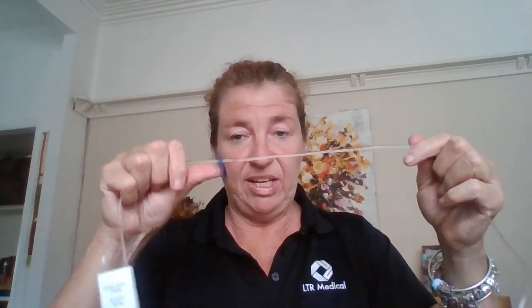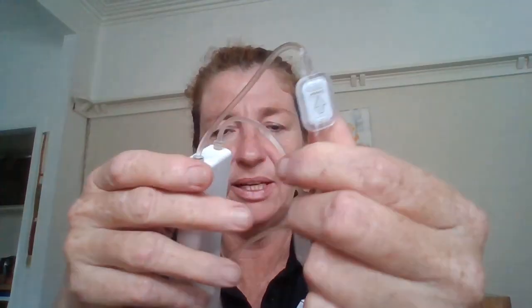This is the filling port here with a one-way valve and a back check valve. From there, we have the remainder of the patient line. Then we have a clamp. Now I recommend not to clamp upon filling the device, and the reason for that is clamping can create a memory in the line. We then have our first filter. You'll notice on the filter it actually has an arrow, and that will be relevant in a moment when I talk about having the arrows pointing upwards during the filling process.